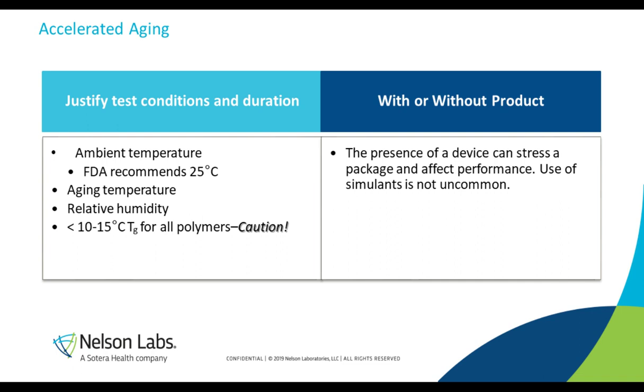The next question that I frequently get is, should I do accelerated aging with or without product? The process of accelerated aging is to look at the effect of the package and the product. So it is important that you do incorporate your product. If your product is super expensive, it is appropriate to use a facsimile device, one with cosmetic defects. Those types of items can be used just as long as they're representative. If you have a medical device and then you decide that you're going to put gauze in there, obviously that's not a good justification. But if you have something that is of similar weight and materials and that is just damaged or something, that's a great option to reduce your costs.